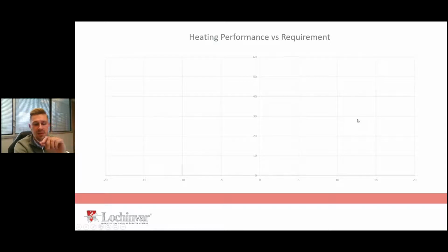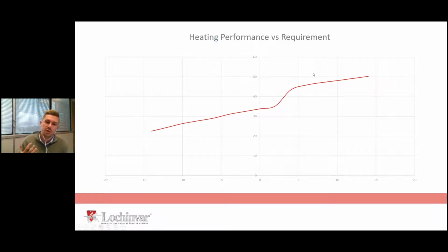So this is a performance table for an electric air source heat pump. And what we have, along the graph on the bottom, is minus 20 degrees centigrade through to positive 20 degrees centigrade on that axis there, look. And then the vertical axis is the kilowatt rating of that electric air source heat pump. So this performance curve you can see at the moment is the output in kilowatts of an electric air source heat pump at various outside air temperatures. This is what I would call a 45 kilowatt heat pump. It is a 45 kilowatt heat pump, very specifically when our outside air temperature is 7 degrees centigrade.